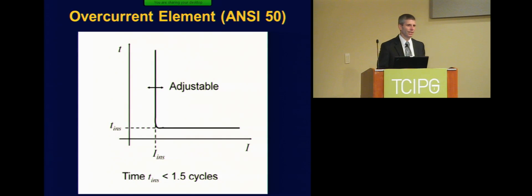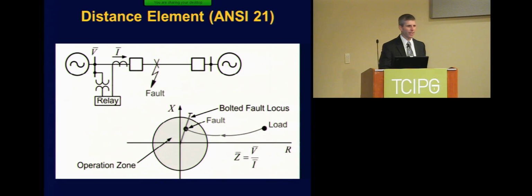Back to the question: do I really need wide area communications to operate the power system? One of the easiest elements is an overcurrent element. If the current's too big, we trip the circuit breaker, no communications required. If we get a bit fancier, we can coordinate protection using voltage and current measurements. Here we have a 21 element, a distance element, where the load is out on the right. Ideally, with a big V and a little I, the impedance is purely resistive, so the load is out to the right. If I have a fault, my V gets really small, my I gets really big, and I come inside this circle, which is set to protect a particular zone in the power system. If I come inside that zone, it's time to trip the circuit breaker. I can have these relays at both ends of the line, and they can coordinate with each other, again no communication required. So we really can operate the power system without communication, we just lose some of the benefits for optimization.